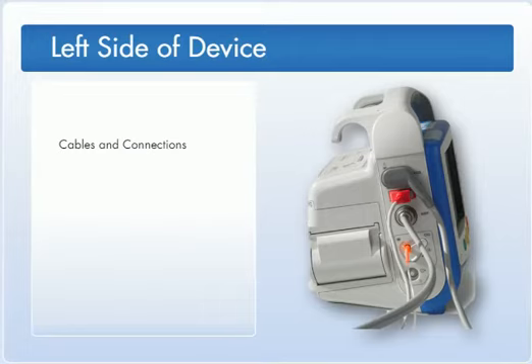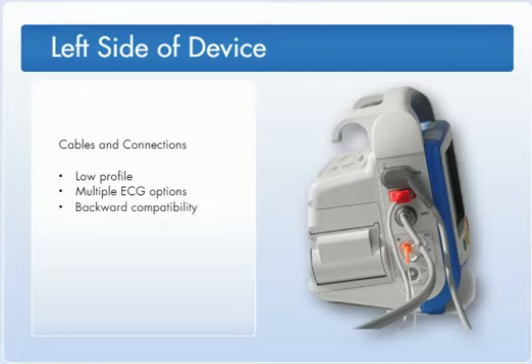All the cabling and connections on the left side of the X-Series have low-profile connectors, making them less obtrusive and more durable. There are multiple ECG options, 3, 4, 5, and 12 lead. In addition, there is backward compatibility amongst the X-Series and ProPaq MD cables for ECG, temperature, and IBP. The Masimo Rainbow cables and sensors are backward compatible with all Zoll equipment using Rainbow technology.